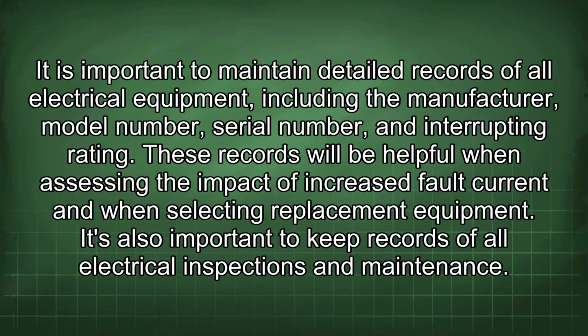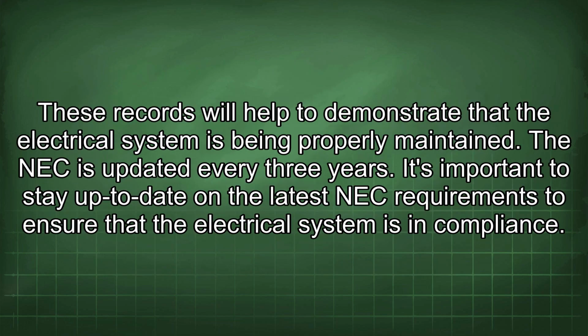It is important to maintain detailed records of all electrical equipment, including the manufacturer, model number, serial number, and interrupting rating. These records will be helpful when assessing the impact of increased fault current and when selecting replacement equipment. It's also important to keep records of all electrical inspections and maintenance. These records will help to demonstrate that the electrical system is being properly maintained.